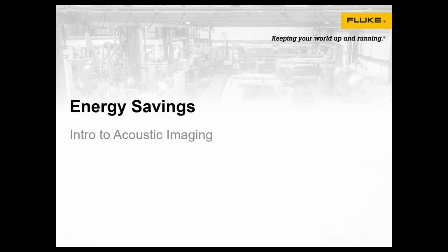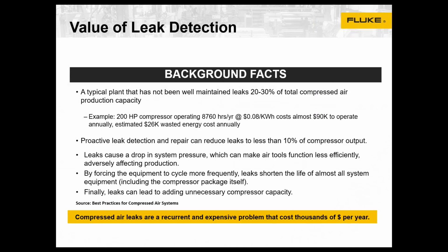So we're going to look at the next aspect of cost savings, namely energy savings, and introduce an exciting new technology called acoustic imaging. But first, let's take a look at, well, how can we save energy? Well, it's really through leak management on compressed air systems. In the US, the Department of Energy has done studies and shows that a typical plant that doesn't have a leak detection and repair program loses anywhere from about 20 to 30% of the compressed air capacity due to leaks.